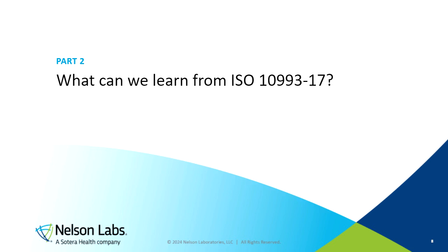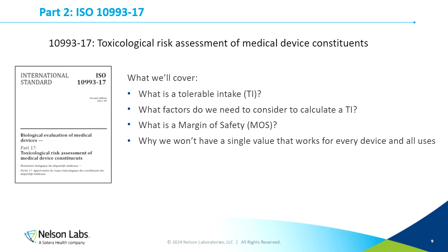Okay, so what can we learn from ISO 10993 Part 17? In this section, I'm going to cover what is a tolerable intake, what factors do we need to calculate a tolerable intake, and what is a margin of safety.